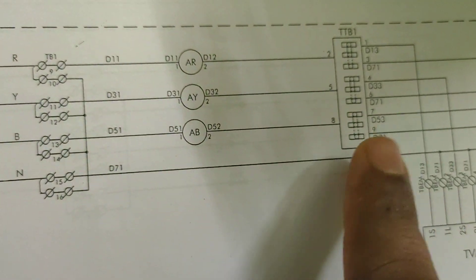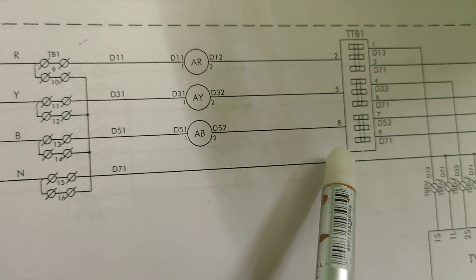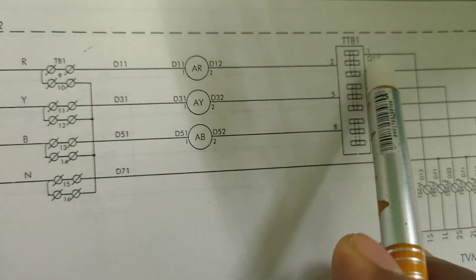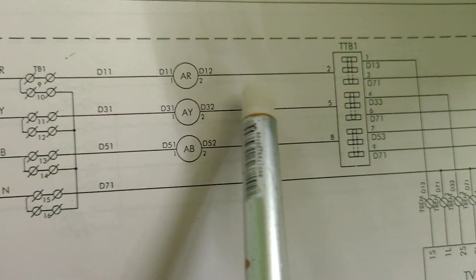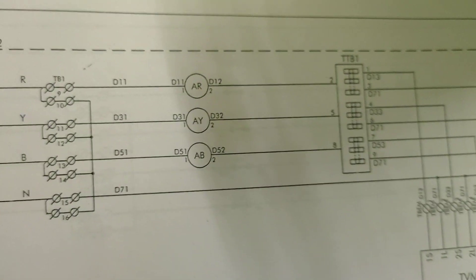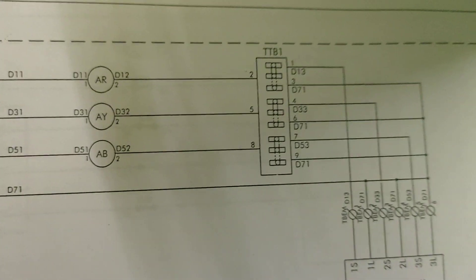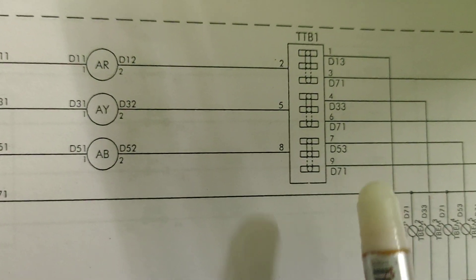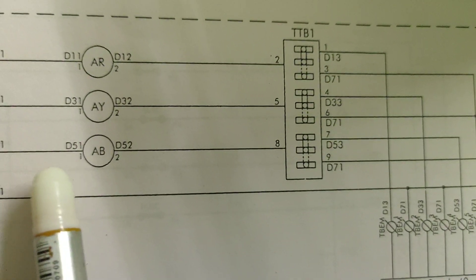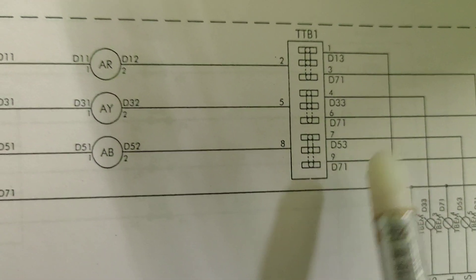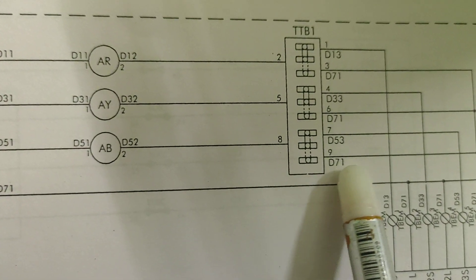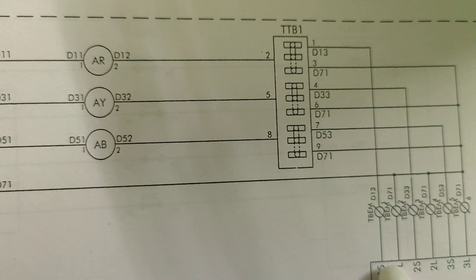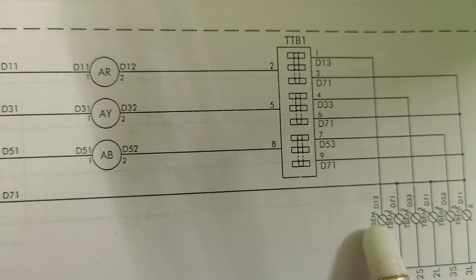After the test terminal block, the ferrule names change: D11 becomes D13, D31 becomes D33, D51 becomes D53, and D71 remains common. So from the TTB we get pairs: D71 with D13, D71 with D33, and D71 with D53.